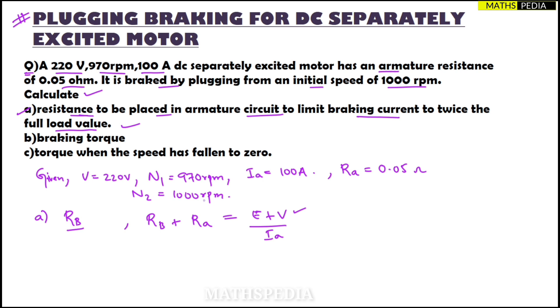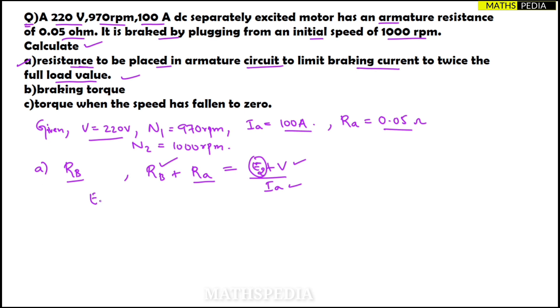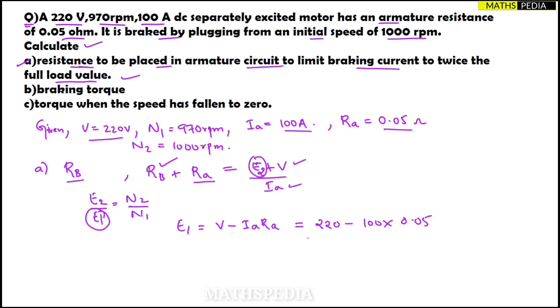We know V = 220 volts and Ia = 100 ampere and Ra = 0.05 ohm. The unknown is E, which we call E2. To find E1 first, we use the formula E1 = V − Ia × Ra = 220 − 100 × 0.05 = 215 volts.